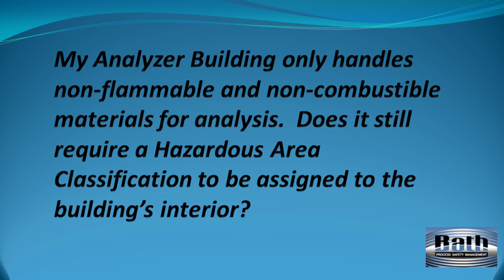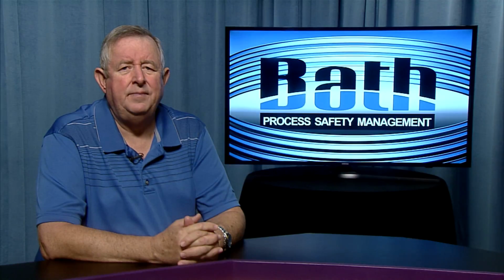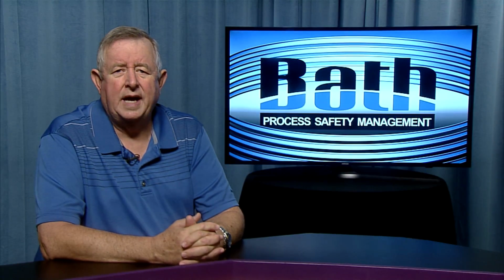Now let's answer the second question regarding analyzer buildings. My analyzer building only handles non-flammable and non-combustible materials for analysis. Does it still require a hazardous area classification to be assigned to the building's interior? The answer is somewhat complicated because several factors impact the assigned hazardous area classification of buildings which house electrical equipment only with no batteries and no piped-in flammable or combustible materials.